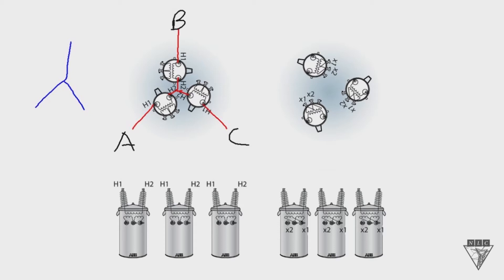So let's move down to the bottom and do our actual connections on the transformers. And once again, we'll tie our H2 bushings together and may or may not go to ground. And then our H1s are each going to go up to a phase. So we've got A phase, B phase, and C phase.